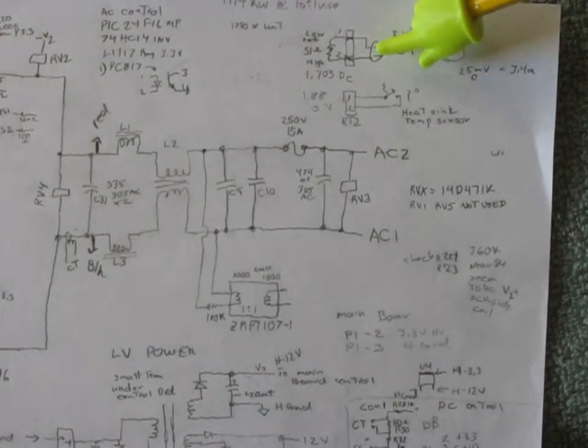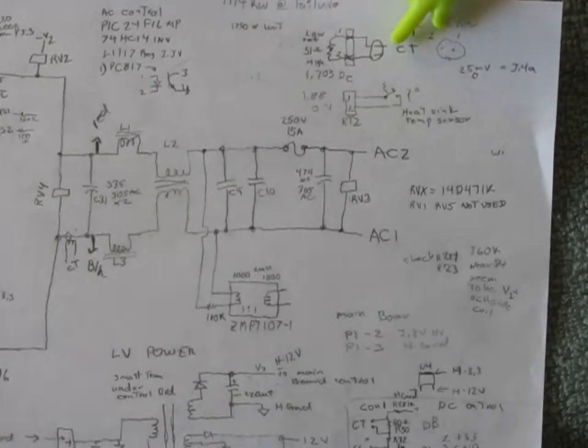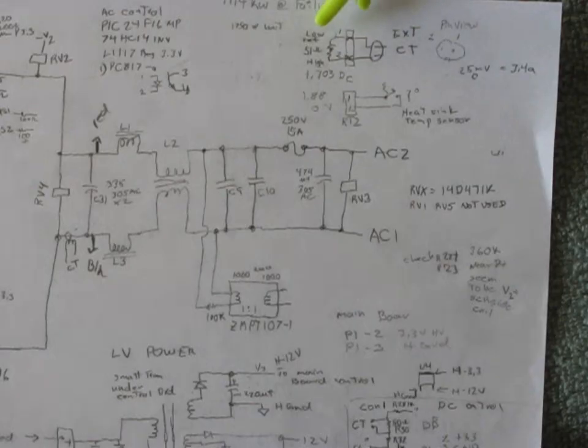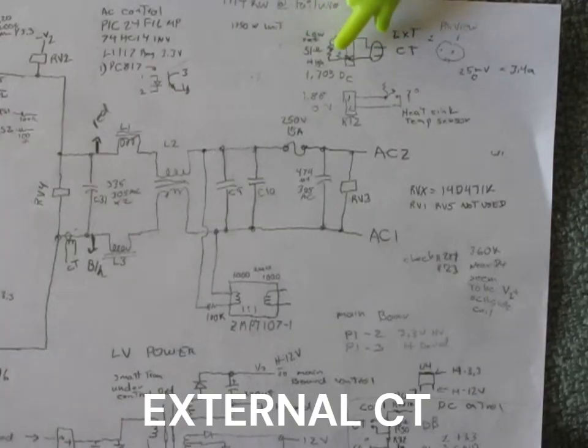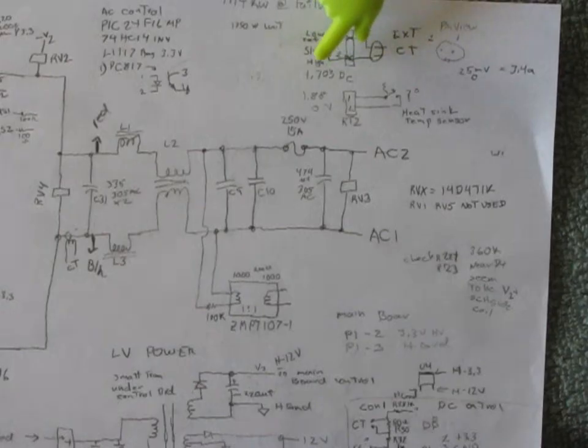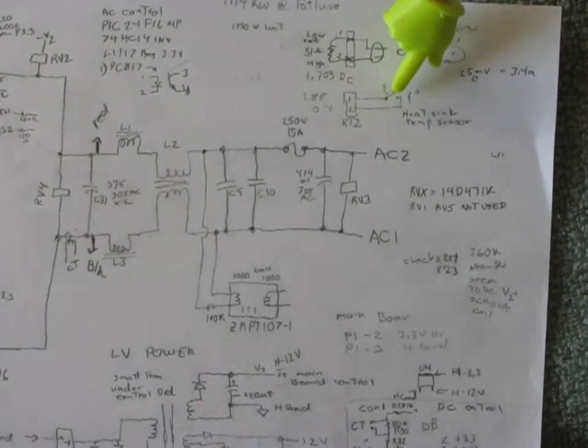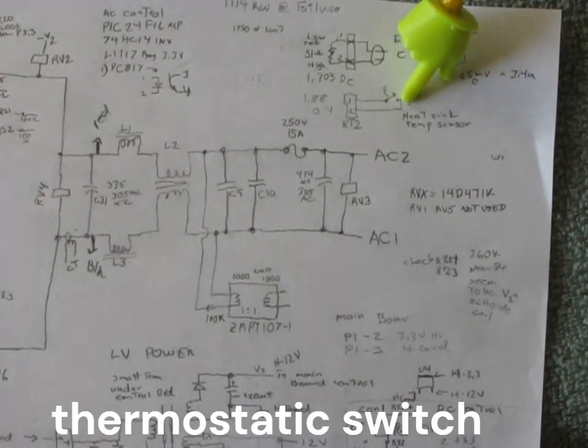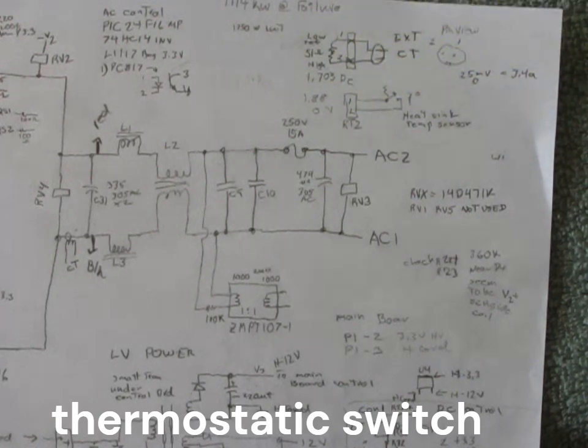It has two designations, 1 and 2, and they go to the DC control board. Looking at the board, there's actually a 50 ohm load resistor across that current transformer, and one side is tied to a 1.7 volt DC reference. The other side, I assume, goes to the conversion circuitry on the DC control board. On one of the heat sinks there's something that looks like a thermistor but is actually a switch, which also goes to the DC control board.